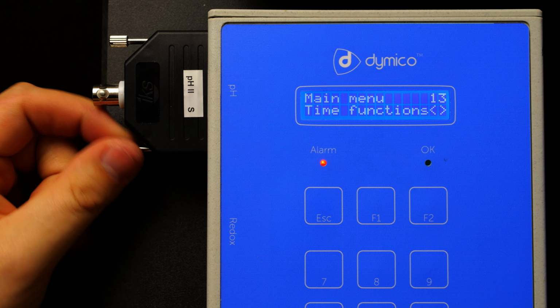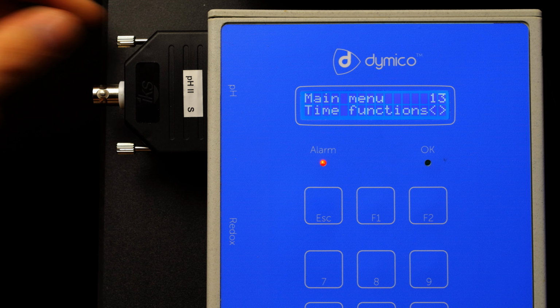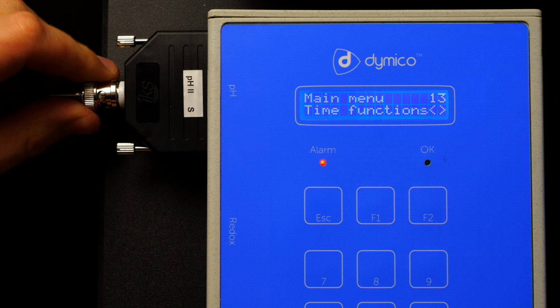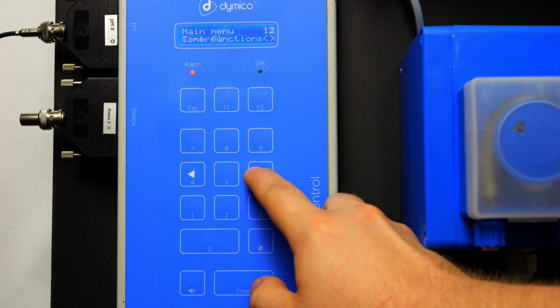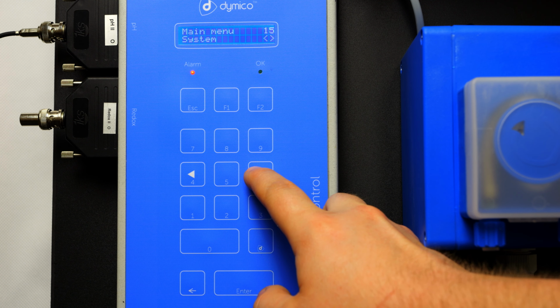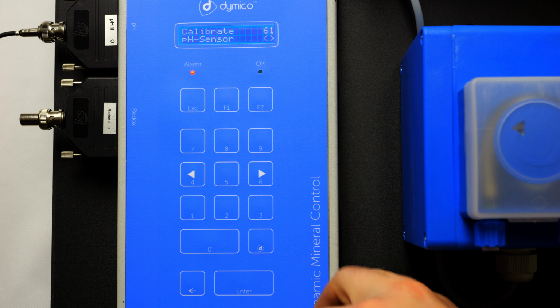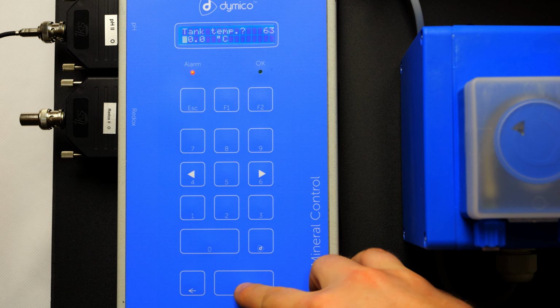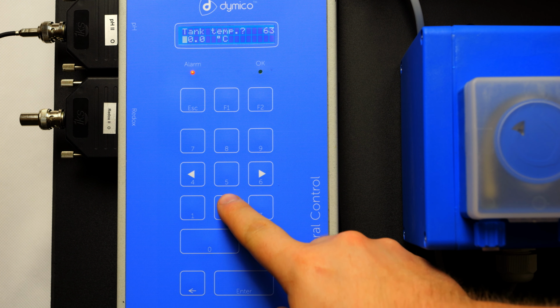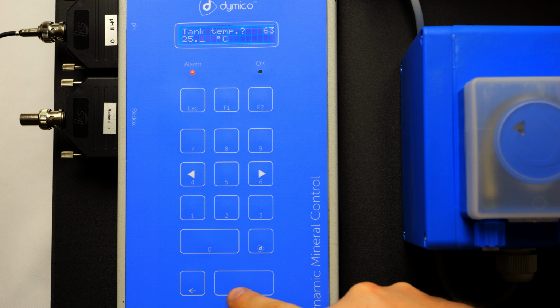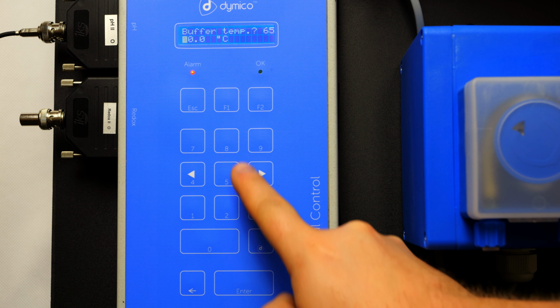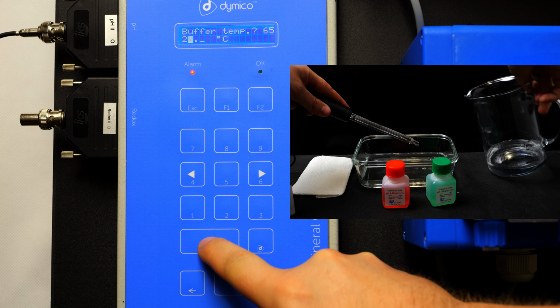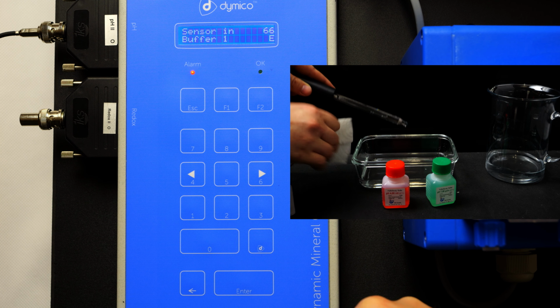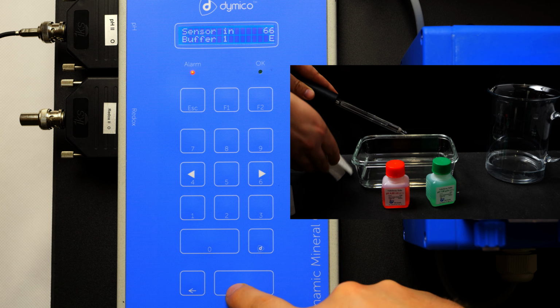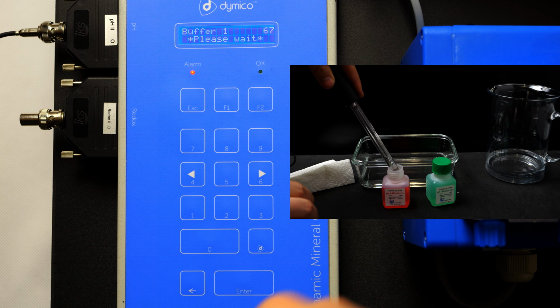Connect the pH module to the sensor 1 socket of the Aquastar. Connect the pH probe to the module. Calibrate the pH probe using pH 4 and pH 7 standards. To do so, enter main menu, calibrate, pH sensor. Press enter to go further, and use the number keys to set the values. Make sure the probe is clean and dry between each step. Use deionized water and paper towel. pH calibration can take a few minutes in each solution.